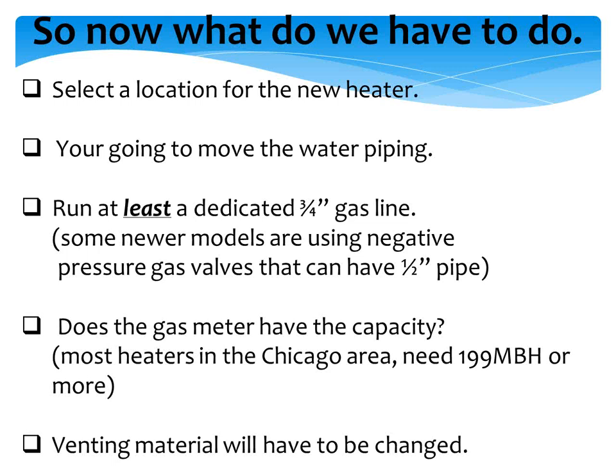And chances are the venting materials are going to be changed also. You're going to be venting PVC pipe for a condensing type heater, or for a non-condensing, you're going to be talking stainless steel venting. So we've got a lot of things to look at when we're out here planning the job. It's not just slapping in a 40-gallon water heater. Mike, is there also usually an electrical connection for controls and stuff like that? The non-condensing models, there are a few of them that aren't using any kind of electric on them. The condensing models are draft induced, all that good stuff. So yes, you're going to have power.